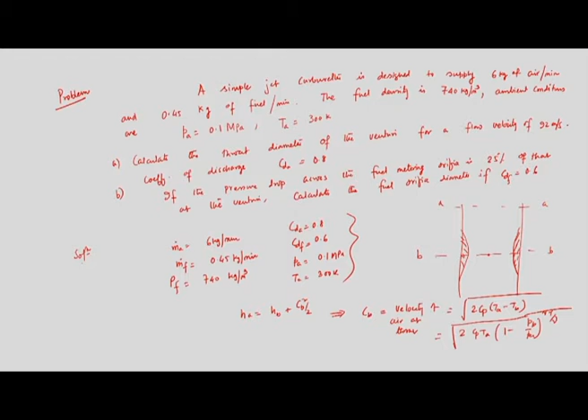The actual air velocity should differ from the ideal air velocity because we did not take the frictional effect into account. So, the actual air velocity should be 0.8 into the ideal air velocity, where 0.8 is the coefficient of discharge of air. The actual air velocity is given, for which we have to calculate the throat diameter of the venturi. Calculate the throat diameter at the venturi for a flow of air of 92 meter per second.